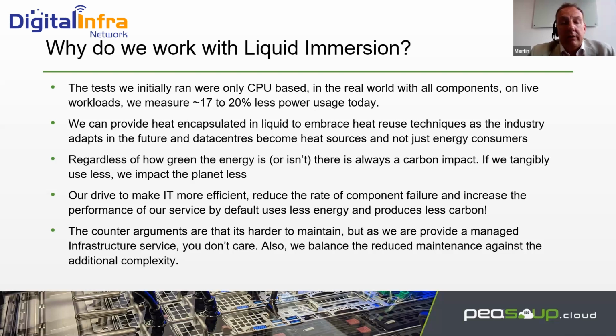What we're also ready for is the heat. Obviously we're going to generate heat, but our heat is encapsulated in liquid. Now the liquid we use at the moment is going off to a chiller because it's part of the air conditioning system for the data center. But we don't need to send it to a chiller, and we've shown that because the level is so much lower, we could raise the base level.